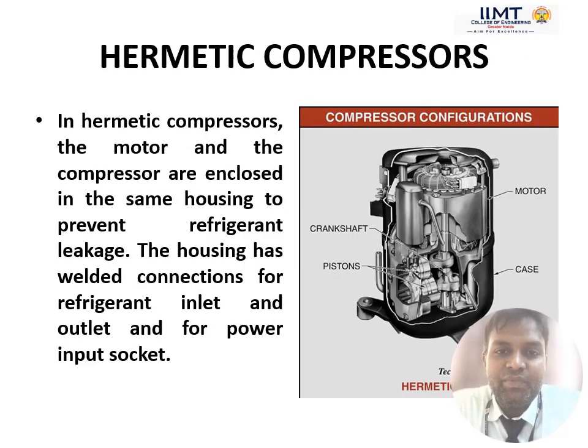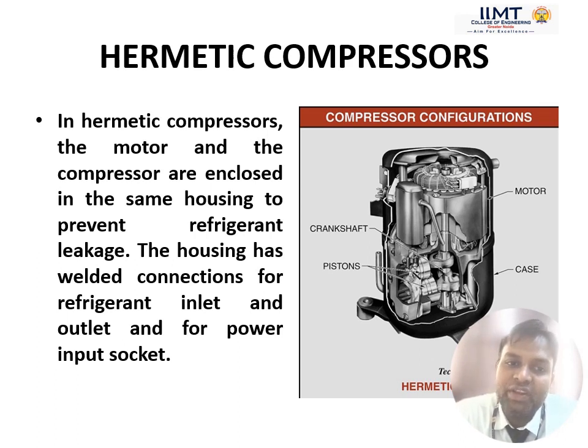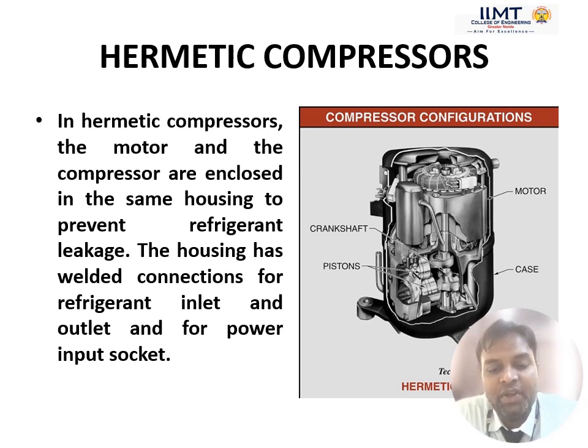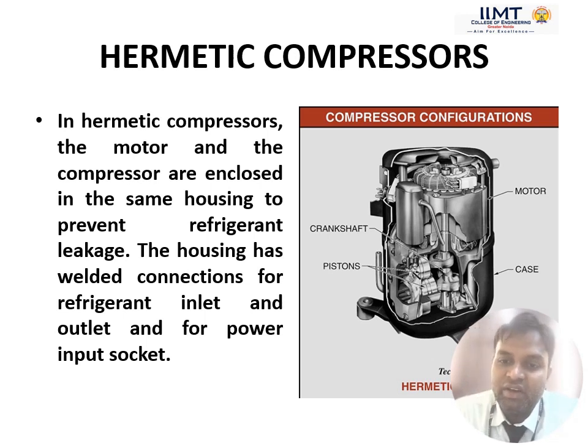The second type is the hermetical compressor. In a hermetical sealed compressor, the motor and compressor are enclosed in the same housing to prevent refrigerant leakage. The housing has welded connections for the refrigerant inlet and outlet pipes as well as for electrical wiring. This is basically what we see in our commercial or home refrigerators — the black box at the back side of the fridge is the hermetical sealed compressor.